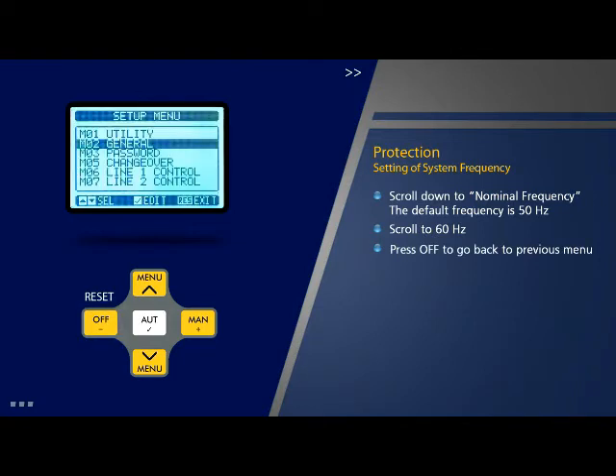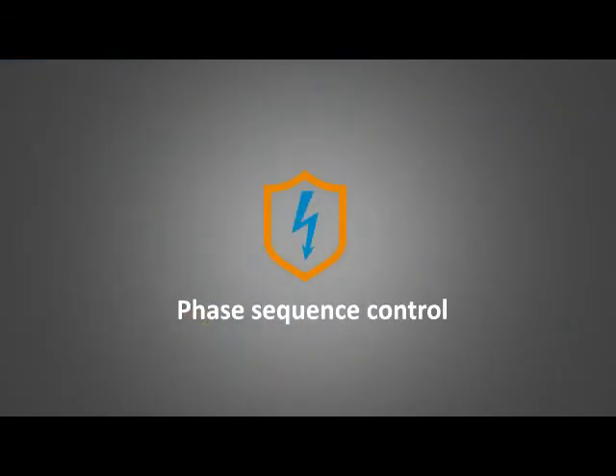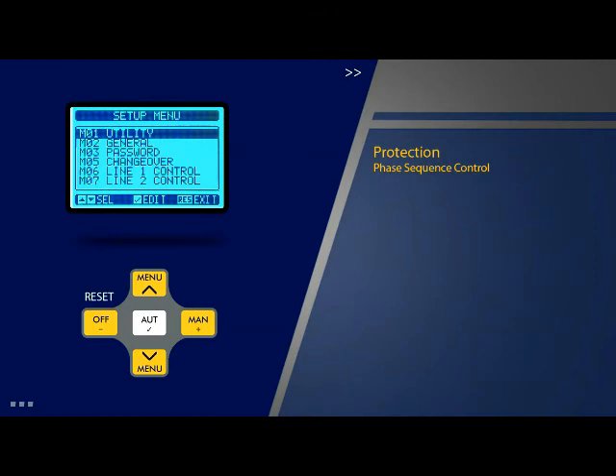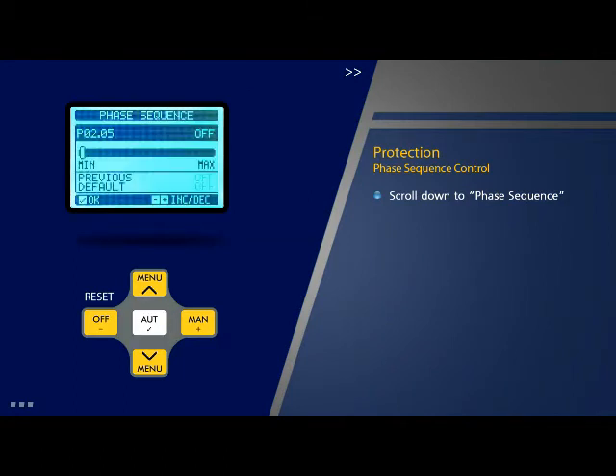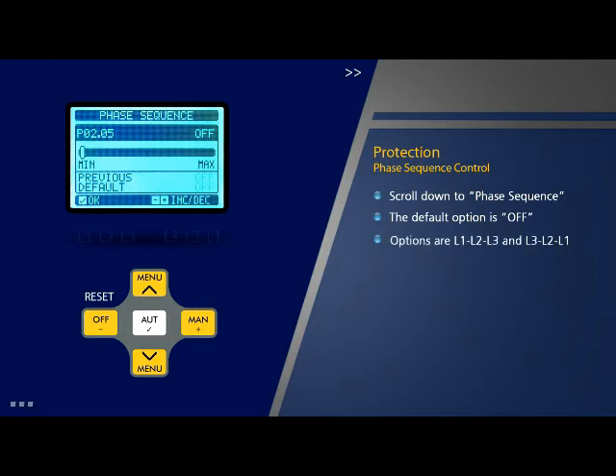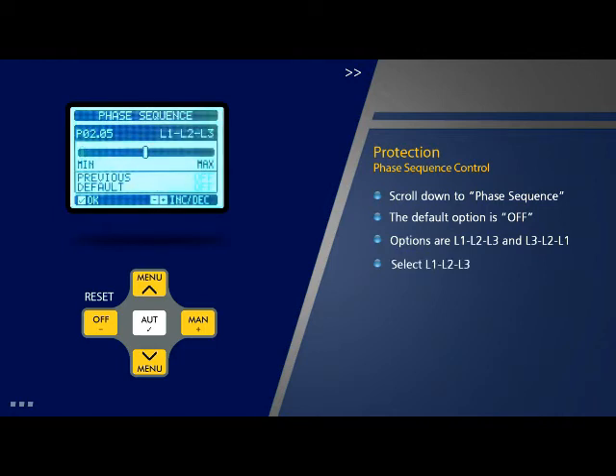Press off to go back to the previous menu. Press off again to go to the home page. Phase sequence control: Scroll down to select parameter 5 'Phase Sequence' on the general page and press OK. The default option for phase sequence is off. The other options are L1-L2-L3 and L3-L2-L1. Select the option L1-L2-L3 and press OK.